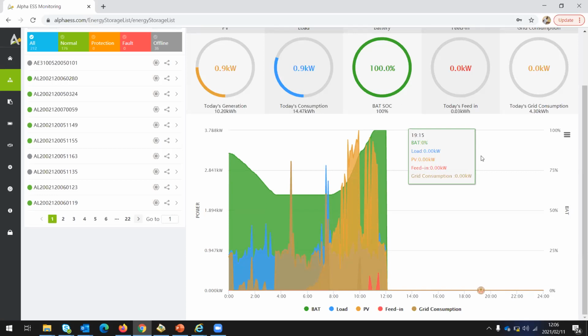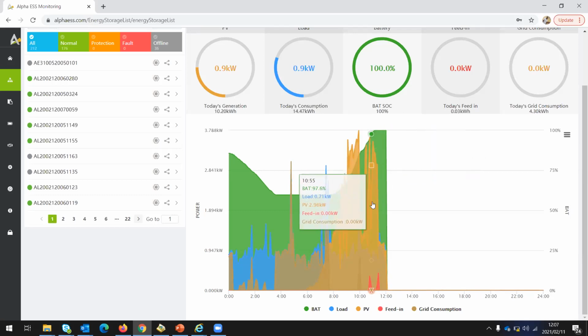Usually, with some digital meters with low reverse current tolerance, you would get them tripping here and there. So you would need to contact us, especially if you have a Conlog. That's the one which usually trips because of its sensitive reverse power current. You would contact us, then we would file with Conlog, and they can widen the tolerance of your meter so that it doesn't trip on that trickle power. Alternatively, you can strike a balance between your battery SOC and your PV array to avoid that trickle power, because trickle power happens when the battery is full, just above 95%, where the battery management system performs trickle charging so as not to damage the cells. That's where you usually get those trickle power.